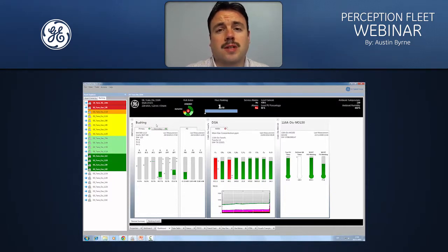Within the DGA section then we have the latest dissolved gas measurement, and you can see we color code the gauges as well to show if any of the measurements have breached an alarm. And then finally we have our MO150 section, which shows additional information such as top oil temperature, bottom oil temperature, winding hotspot HV temperature, and winding hotspot TV temperature. So any additional information that's captured by the MO150 or the Hydran M2 with models that's seen as being critical is output to this section as well. Just as well at the bottom of the DGA section you'll see that we have a small TDCG graph. This is our total dissolved combustible gases chart, and it just gives you a snapshot of the gases within the asset over a period of time to show you if your gases are increasing or falling over time.